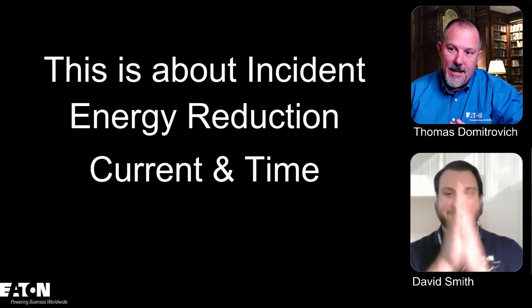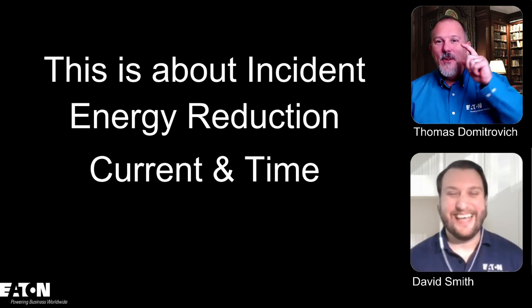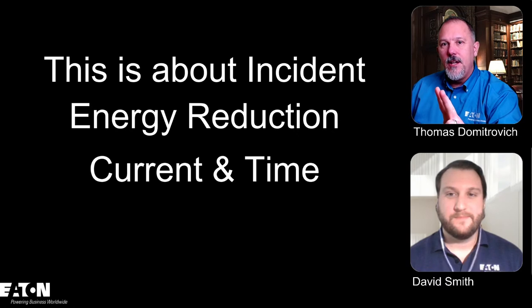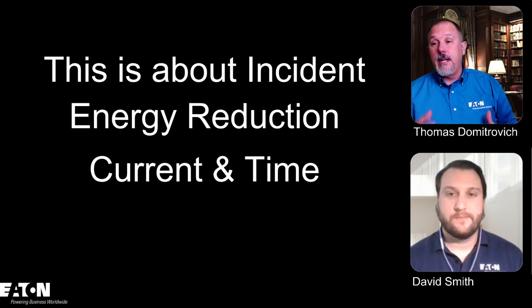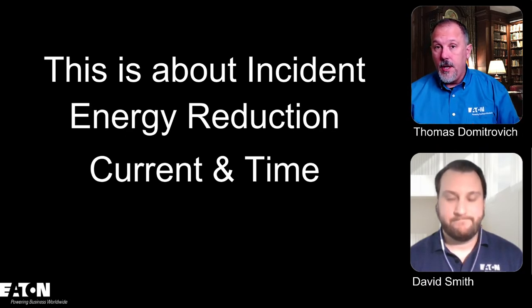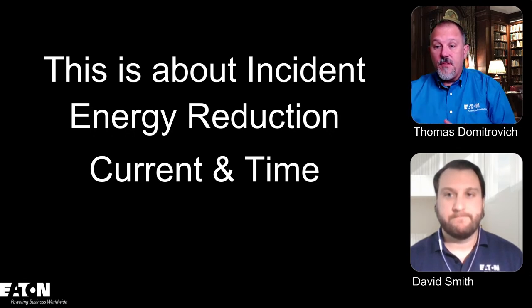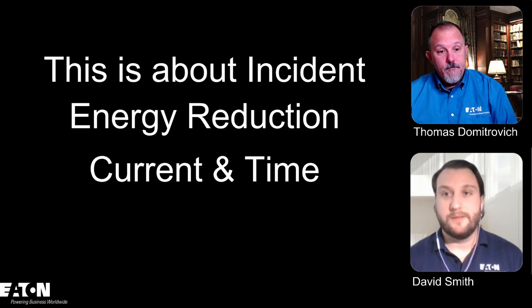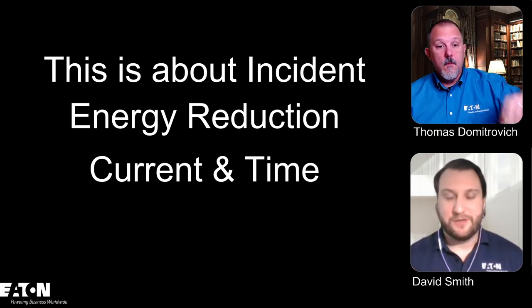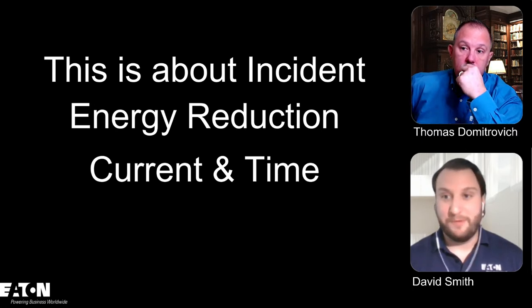Okay. I know we're going to get deep into this. And you know, current and time are two very critical factors when you're talking about incident energy. But if I'm truly talking incident energy, there are a couple other things that impact how much energy the electrical worker is going to experience when an event occurs, if an event occurs. And that happens to be the size of the enclosure and the configuration of the bus. That's right. Sure. Yeah. Yep. And so just to go off of that a little bit, if we're talking about energy, current and time make up, if you multiply those, you're talking about energy. It's energy over time times time. So what we are specifically talking about today is reduction of energy.